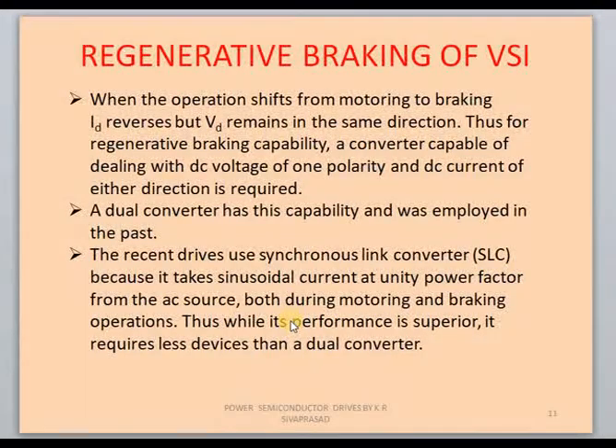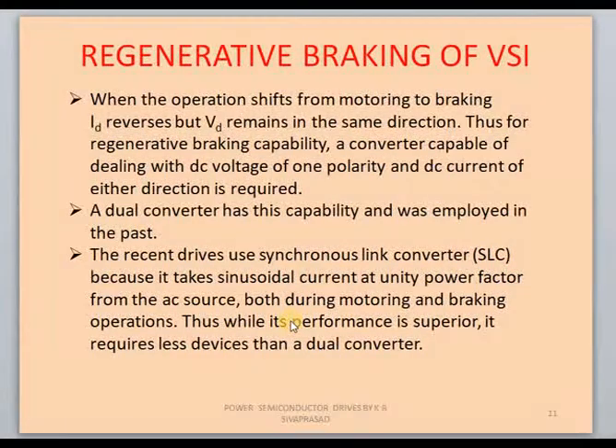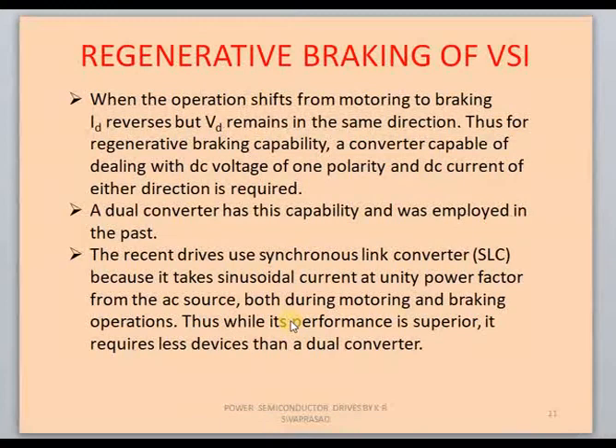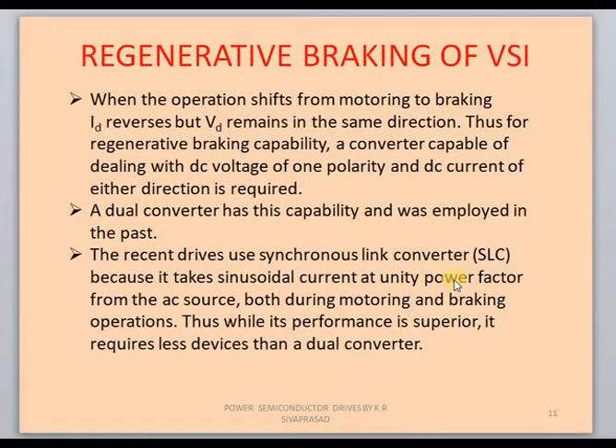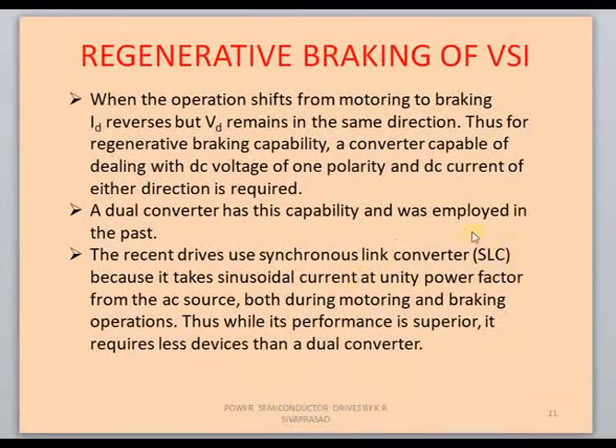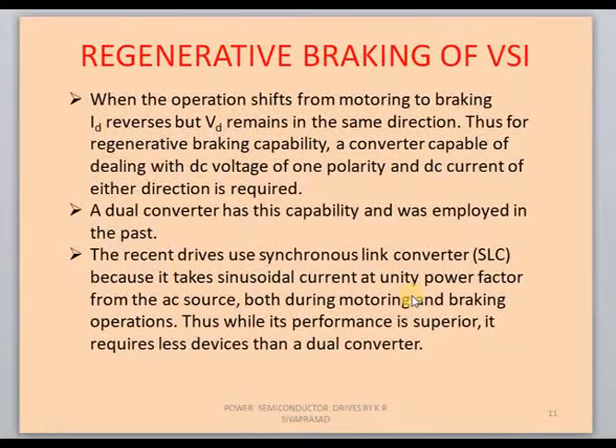For regenerative braking of VSI, we need the direction of I_d to change with a constant V_d value. This is possible using a dual converter or, in recent trends, a synchronous link converter (SLC). Synchronous link converters operate similarly to a synchronous motor — their phasor diagram resembles that of a synchronous motor, hence the name. The major advantage of the synchronous link converter is it always maintains unity power factor at the input side, both during motoring and braking operations.